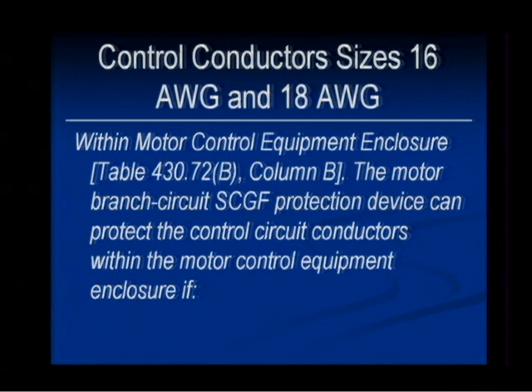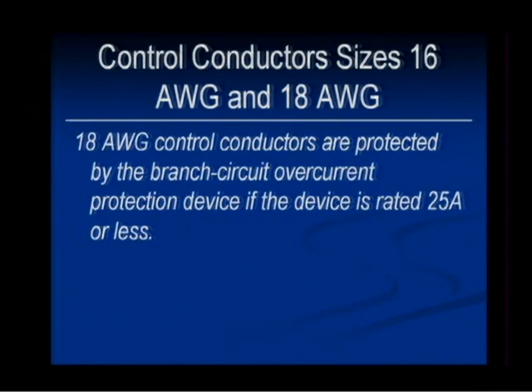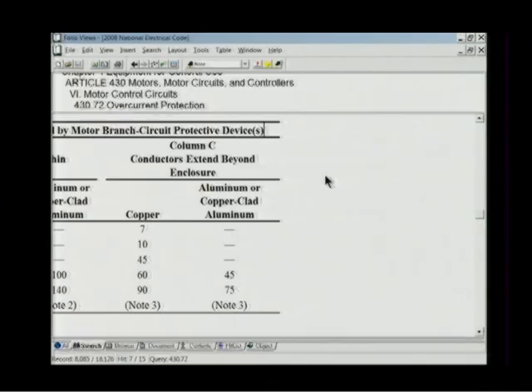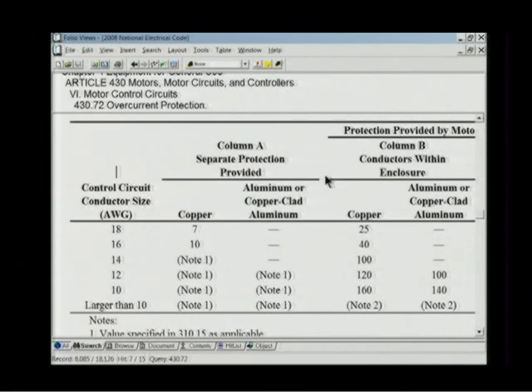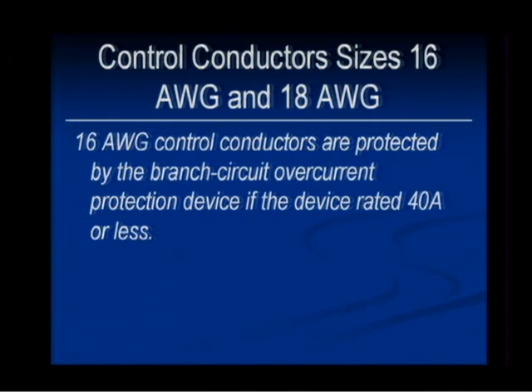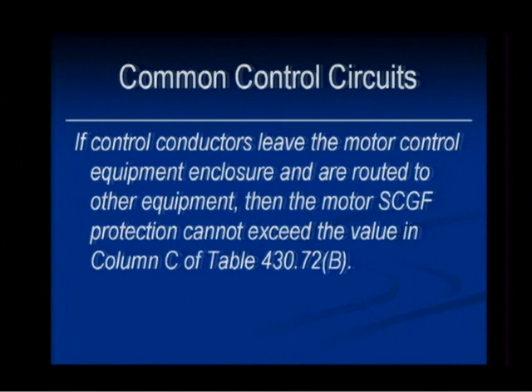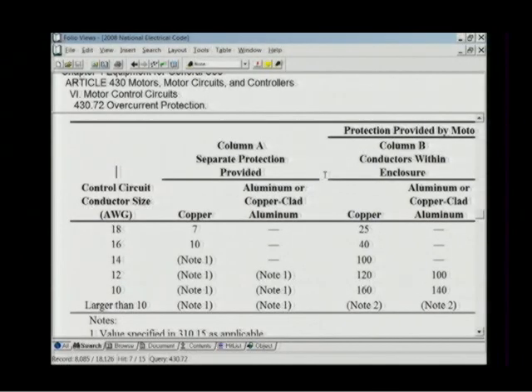And that part about within the enclosure is column B. And we're not going to worry about the conditions of those numbers because we've already seen that here on table 430.72(B), dealing with the 18 gauge wire, 25 amps, we just talked about, the 16 gauge wire, 40 amperes. Now, if the control conductors leave the motor control equipment enclosure and are routed to other equipment, then the motor branch circuit ground fault protection device cannot exceed the values given in column C. So let's take a look at that example.